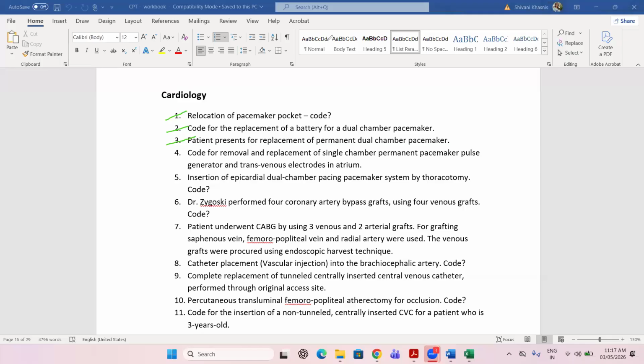And as you could see, a dual chamber pacemaker will always be transvenous. It cannot be epicardial, it cannot be leadless. Epicardial is when you place it over the surface of the heart, not inside the chambers of the heart. And leadless is only in one compartment, where you place all the batteries and electrodes. So it cannot be leadless also.